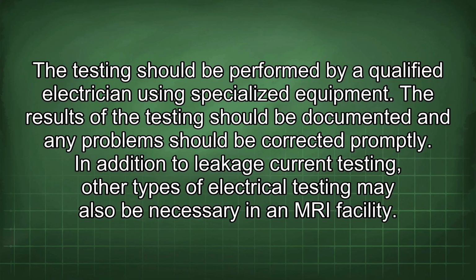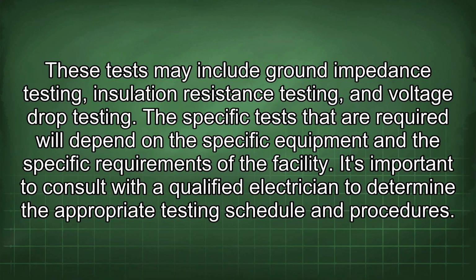The results of the testing should be documented and any problems should be corrected promptly. In addition to leakage current testing, other types of electrical testing may also be necessary in an MRI facility. These tests may include ground impedance testing, insulation resistance testing, and voltage drop testing. The specific tests that are required will depend on the specific equipment and the specific requirements of the facility. It's important to consult with a qualified electrician to determine the appropriate testing schedule and procedures.